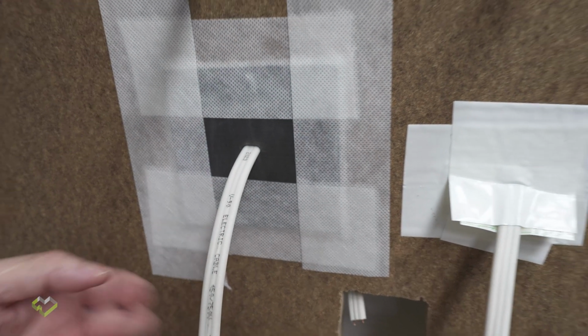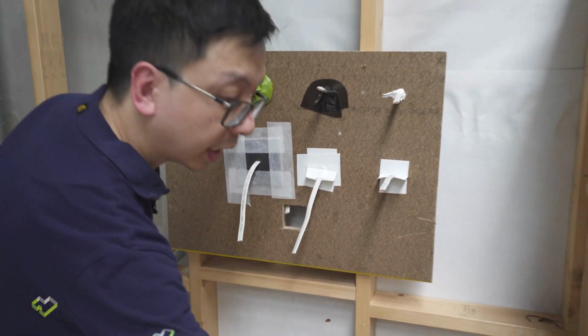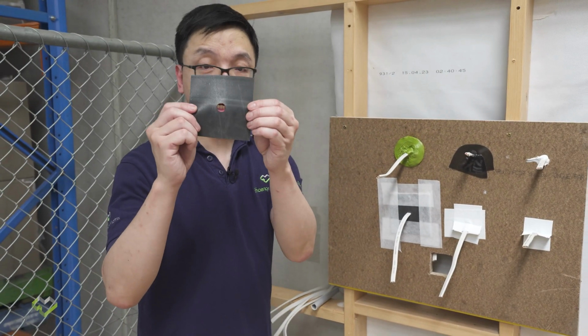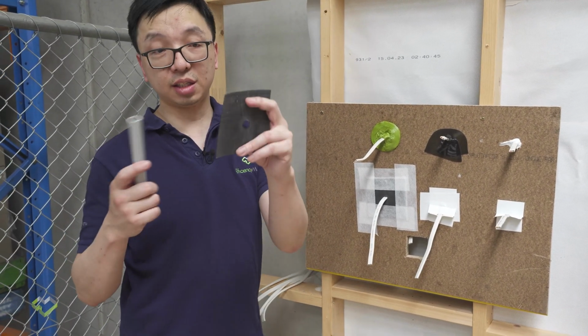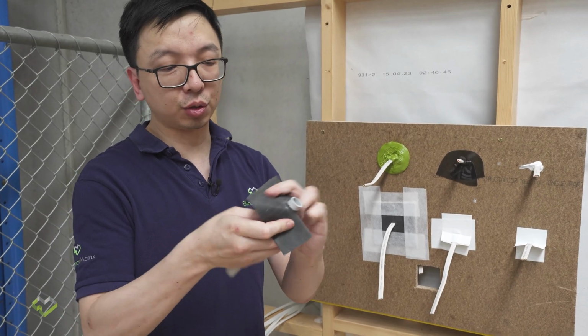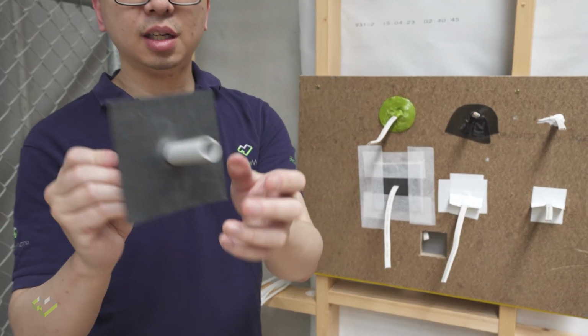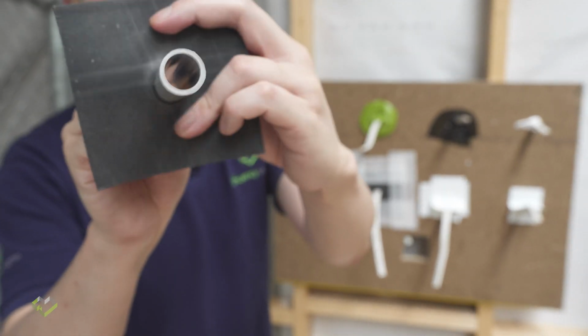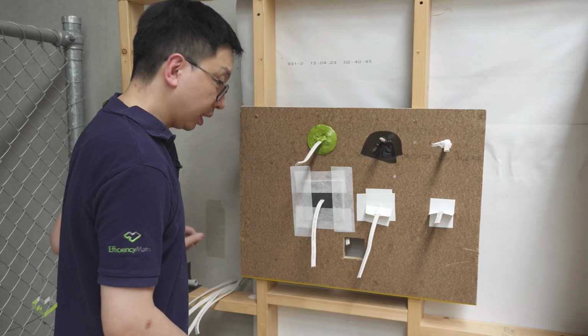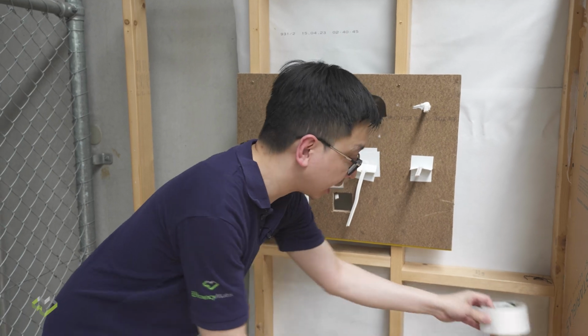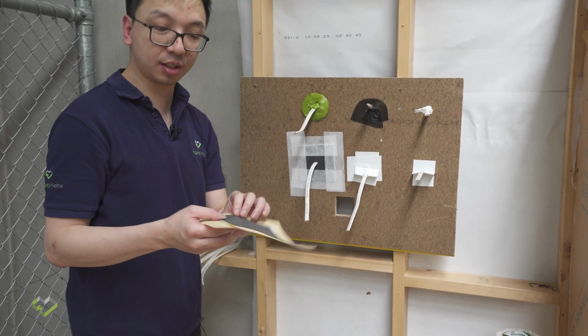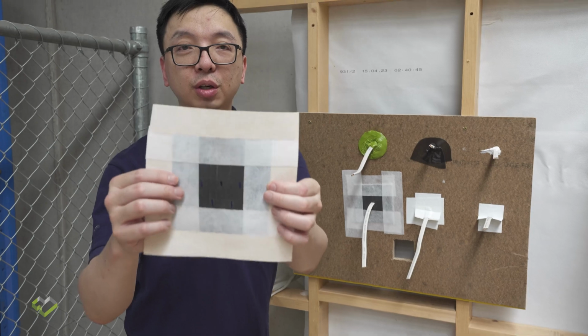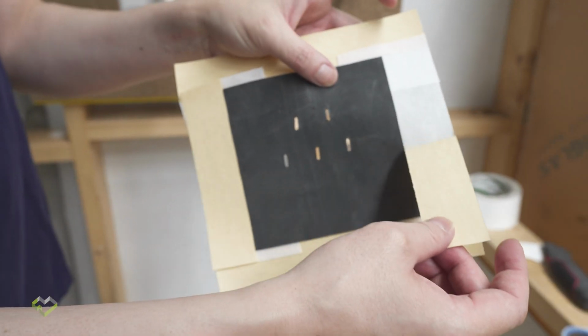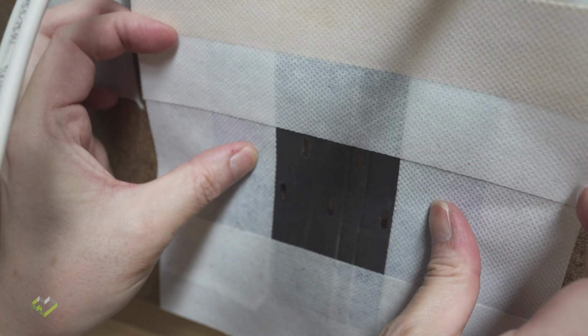And you can use different size hole punchers, depending on how thick the cable is. And likewise, you can get the pre-cut circular gasket that is more suitable for pipes and conduits. Same process, it creates a tight seal. It allows you to keep moving the conduits. And similarly, if you got one bigger hole with multiple penetrations, you cut the hole, pre-apply the tape with a split backing release liner. That way, the process can be a lot easier.